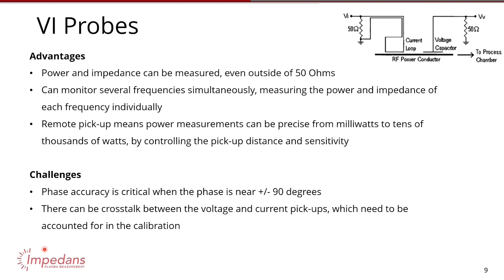Some of the challenges, though, as I mentioned, you need to know the phase in order to know the power. So the phase accuracy is critical, especially when the phase is near plus or minus 90 degrees between the voltage and current, because the cosine of the phase is how you get the power, and the cosine changes rapidly near 90 degrees, plus or minus. Another thing is there can be crosstalk between the voltage and current pickups, but this can be calibrated out if you're clever with the calibration.